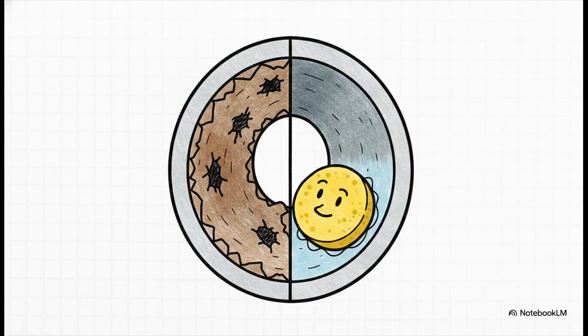And keeping those tubes perfectly spotless does a lot more than just save on the electricity bill. It prevents what engineers ominously call lethal crevice corrosion. If scale builds up unevenly, forming thick patches, it triggers this terrifying chemical reaction right underneath the scale. And that reaction can literally eat holes straight through incredibly expensive metal condenser tubes. By continuously sending these sponge balls through, the ATCS ensures uniform water quality and stops localized scale dead in its tracks, drastically extending the life of the equipment.